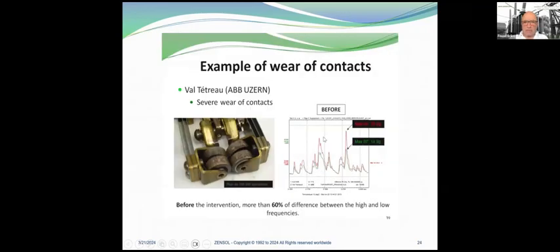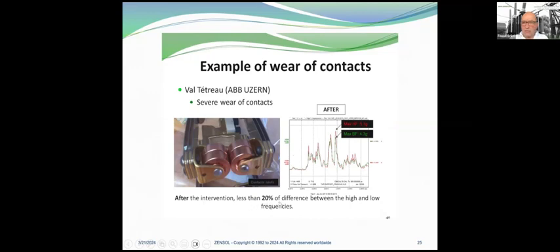Here you have an example of wear of contacts, and how we use the high frequency and low frequency envelope. Before the intervention, there is more than 60% of difference between the high and low frequencies. So this gives us an indication that we have several worn contacts. And after repair, you can see in the next slide, after the intervention, less than 20% of difference between the high and low frequency. So in our report, we have a systematic analysis of these two high frequency and low frequency envelopes, to be able to have an indication of the status of the contacts.